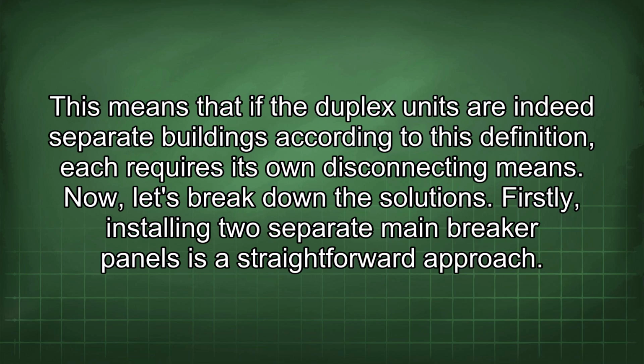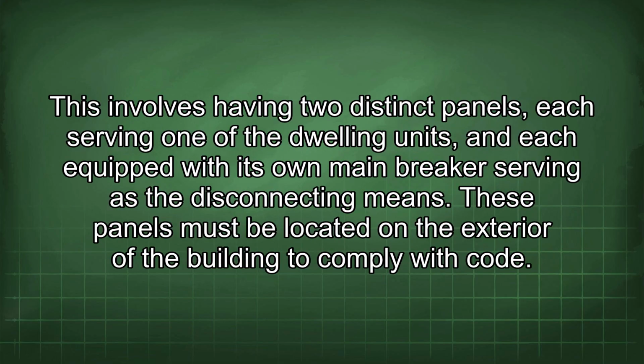Firstly, installing 2 separate main breaker panels is a straightforward approach. This involves having 2 distinct panels, each serving one of the dwelling units, and each equipped with its own main breaker serving as the disconnecting means. These panels must be located on the exterior of the building to comply with code.